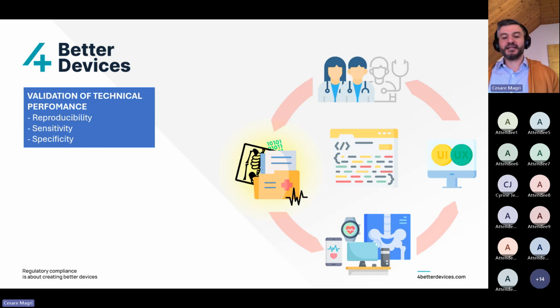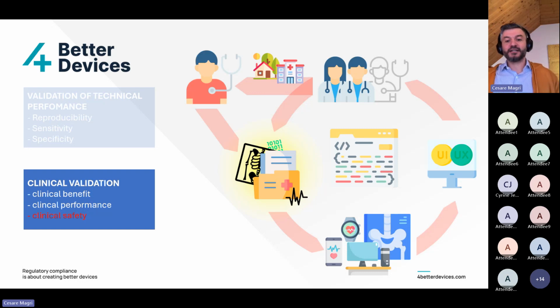Those data might be available in hospitals already, in records, in praxis, and it's very tempting to go and get this data and then perform this calculation on this data, which is perfectly fine, but it's not the end of the story. That's the problem. So in a clinical development plan, that would definitely be one of the points. You want to test the technical performance of your device. You want to know what the sensitivity and specificity of your diagnosis is, but that's not the end of the story. The problem is that instead, the manufacturer gets the feeling, I've done something, a step toward clinical, and I stop there. And in this, they forget the second cycle, which is the cycle related to the patient.